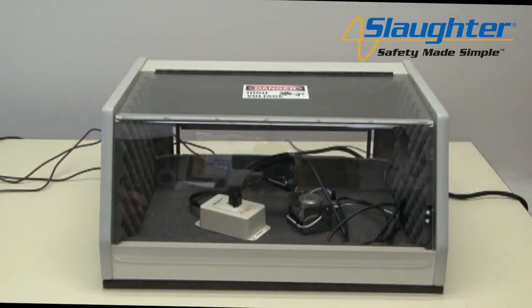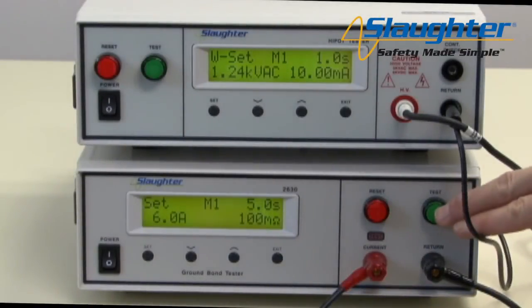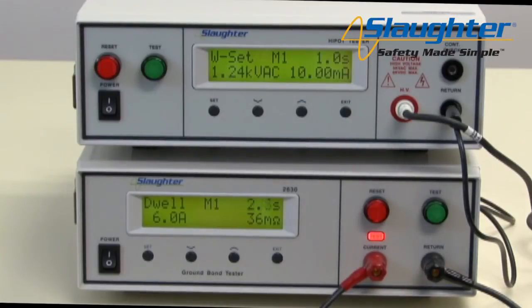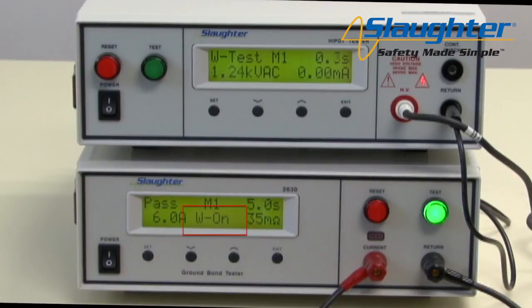Close the DUT enclosure door, stand back, and push the test button on the 2600 to run your test sequence. The 2600 will act as the master unit in the system, so you only need to start the test from this tester. The Hipot test will start automatically. When using this system, you will notice that the 2600 will automatically sense when high voltage is active. The display on the 2600 will change to show a W on, indicating that the dielectric withstand test is processing. The initialization of the Hipot test will now be controlled by the 2600 through the interconnect cables. To review your results, simply press the up and down arrow keys on the 2830 and 2600.